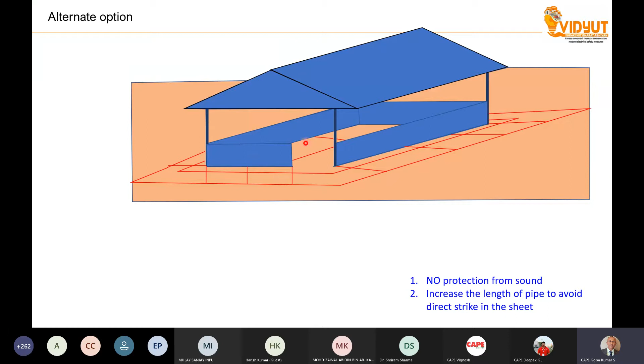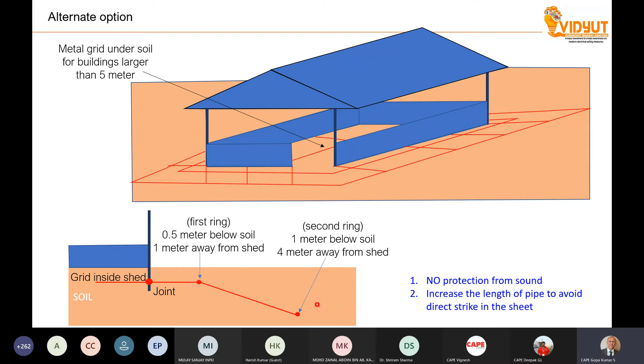Probably all four sides of the building can be covered with metal sheet. As a result, you achieve the particular safety. And this is how the ring conductor shall be extended. The first ring conductor is 0.5 meter below soil, 1 meter away from the shed, and the second one can be about 1 meter below soil, but 4 meters away from the building.